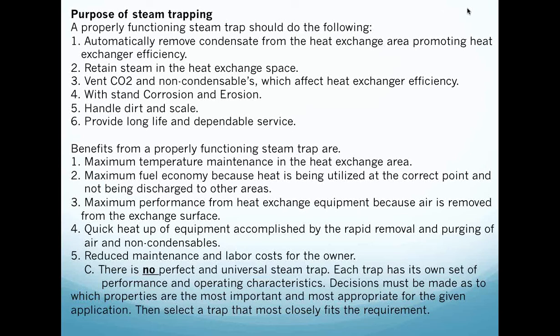So that trap manufacturer and that trap technology got a bad rap, if you will, because it wasn't able to process all that garbage that they had shoved into it. A steam trap should be able to handle dirt and scale to a certain extent. We put strainers in front of trap technologies, and I want you all to know right now, please, please, please be very careful with your strainers and make very certain that you have nipples and blowdowns on your strainers.